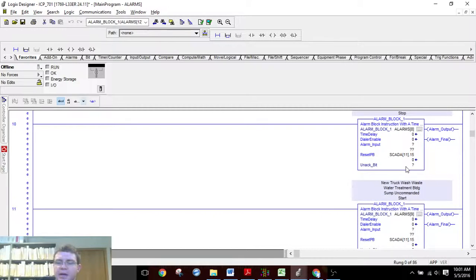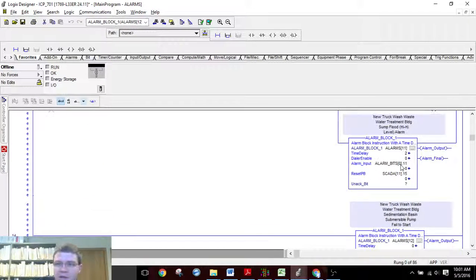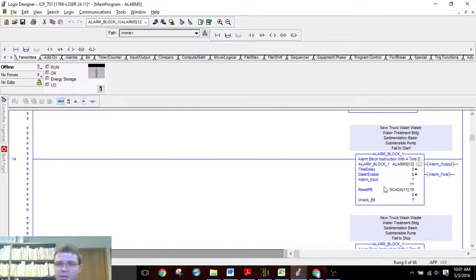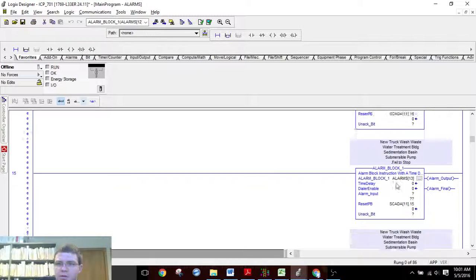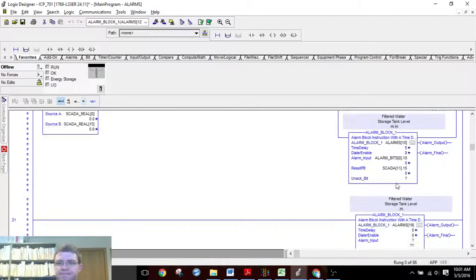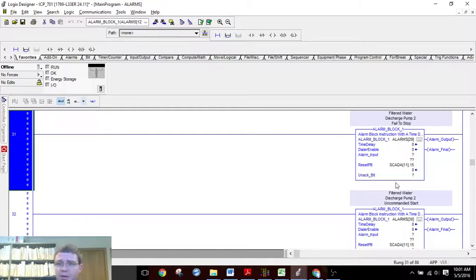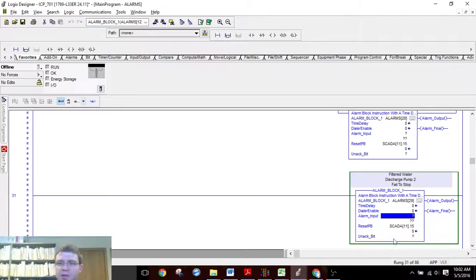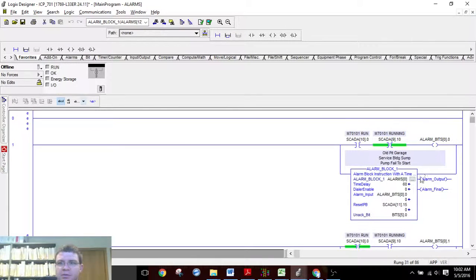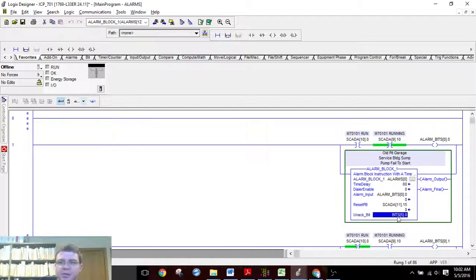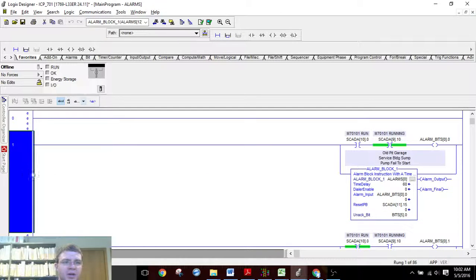As you can see, SCADA 1115 has been inserted into all of these, so it looks like we did it successfully. For the next video I'm going to work on a way to insert the alarm input and also the unacknowledged bit into each of those, which are going to be unique for each one. As you can see here this is a finished alarm — we'll have our alarm bit zero activated by all alarm conditions, and our unacknowledged bit which will be incremented. I'm going to work on that in Excel to find a solution so I don't have to click and replace each and every one of these alarms. Thank you very much.